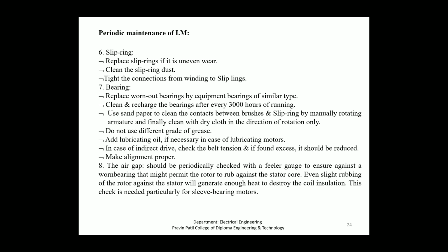Next is the air gap. The air gap should be periodically checked with a feeler gauge to ensure against a worn bearing that might permit the rotor to rub against the stator core. Even slight rubbing of the rotor against the stator will generate enough heat to destroy the coil insulation. This check is needed particularly for sleeve bearing motors.